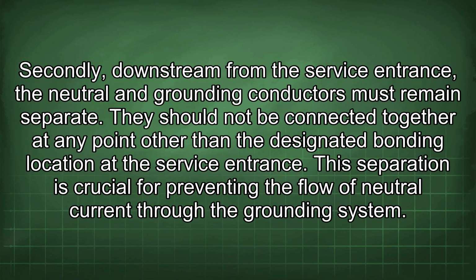Secondly, downstream from the service entrance, the neutral and grounding conductors must remain separate. They should not be connected together at any point other than the designated bonding location at the service entrance. This separation is crucial for preventing the flow of neutral current through the grounding system.